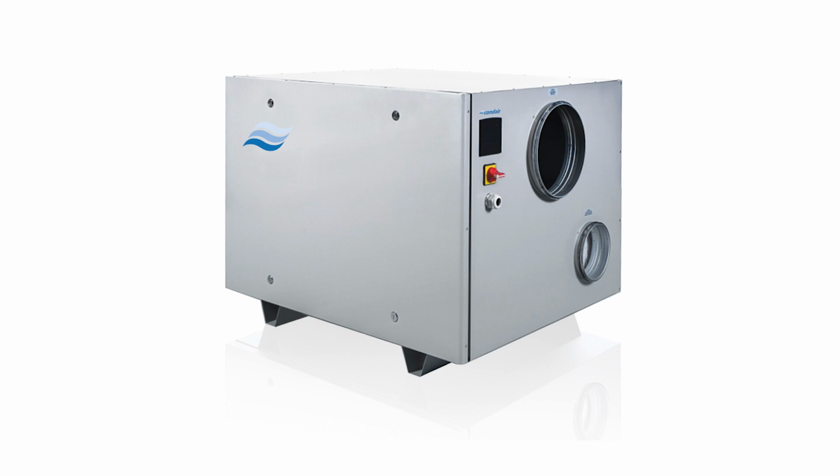And to further reduce the energy use, heat recovery can also be put on the outgoing regeneration air. This scavenges some of the heat from the exhaust air prior to release outside. And using both strategies could significantly reduce the energy needed to heat that regeneration air. Okay. Are there any other drawbacks of using desiccants?